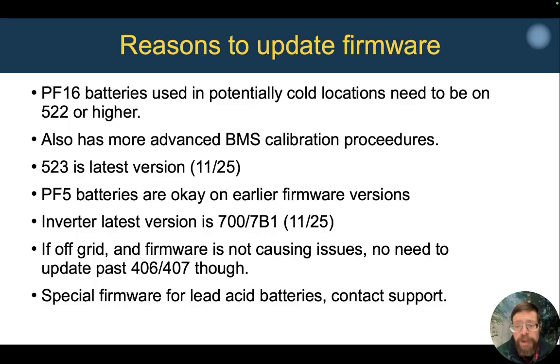Reasons why you might want to update the firmware: if you've got the PowerFlow 16 batteries in a potentially cold location, they need to be on firmware version 522 or higher. This is pretty much late 2025 when they started shipping with that, so any newer or older ones will likely be on 515 or 510 and need to be updated for the heaters to work properly.